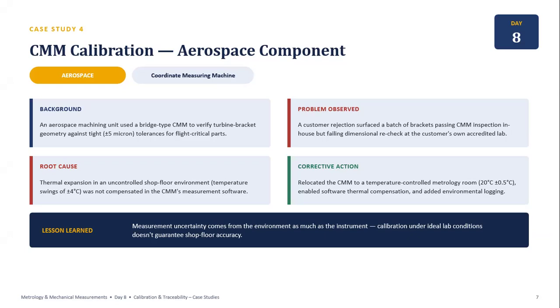The corrective action included relocating the CMM to a temperature-controlled metrology room maintained at 20 degrees Celsius plus or minus 0.5 degrees Celsius, enabling thermal compensation and introducing environmental logging. The lesson is extremely important. Measurement accuracy depends not only on the instrument but also on the measurement environment.